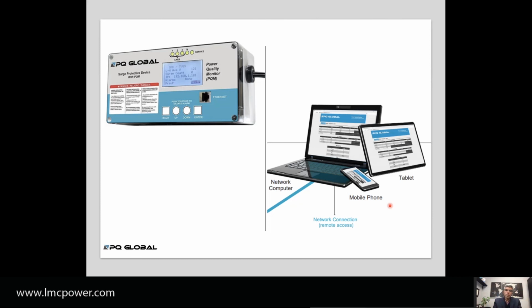Also, it's a power quality monitor, so it also monitors voltage variations. It can give you up to 2,000 readings of how many times the voltage has gone up or down, voltage total harmonic distortion on the voltage side, and how many times there have been power outages. With the Ethernet connection, you can plug it in and download it to your laptop, or have it on your internet system so you can remotely access the information on your iPad, phone, or computer.